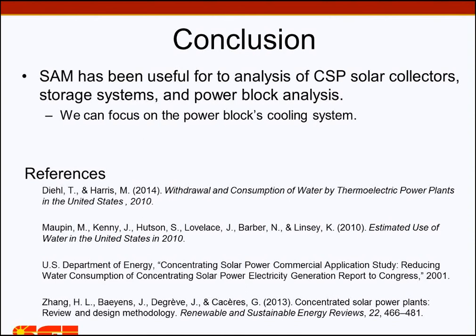I take these numbers and then model a condenser and cooling system of my choosing, to see how I can do in terms of reducing the parasitic loads. From the System Advisor Model hourly results, I can also estimate the steam condensing temperature — the condensing pressure was output, so I can derive the steam condensing temperature. That's shown in the dots, and the ambient air for that week is shown in the green dotted line. With my assumption that I can achieve the same condensing temperature with alternative condenser designs, I can compare the results.